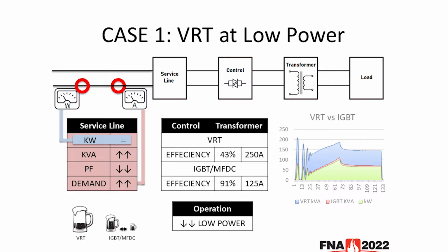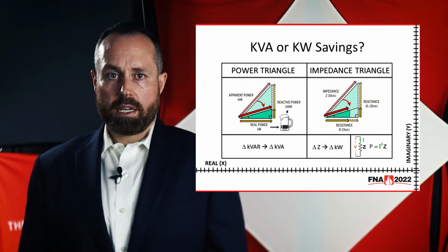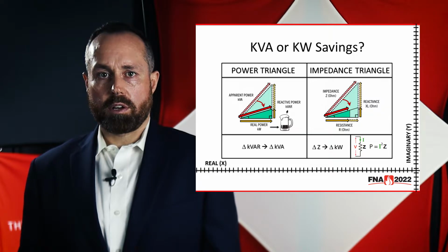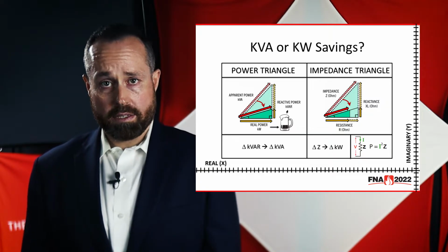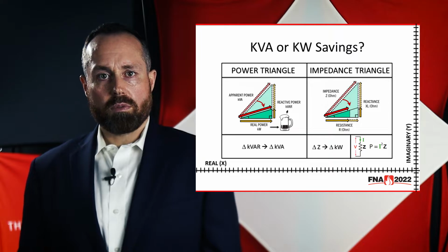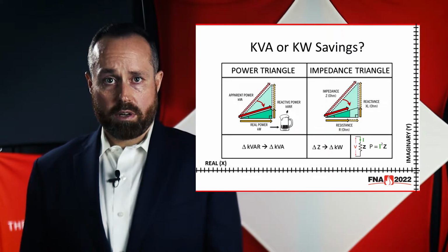The graph here shows the same run, but now with an IGBT MFDC power supply in red. The total power, kVA, is very close to the real power, kW, of the furnace. In summary, for case 1, VRTs running at low set points put a disproportionate burden on the power grid. An IGBT MFDC power supply is an adaptable alternative that optimally shrinks its footprint for each use case. Before moving on to case 2, this is a good opportunity to clear up the difference between kW and kVA savings. Up until now, we've really just discussed the kVA portion of the story.